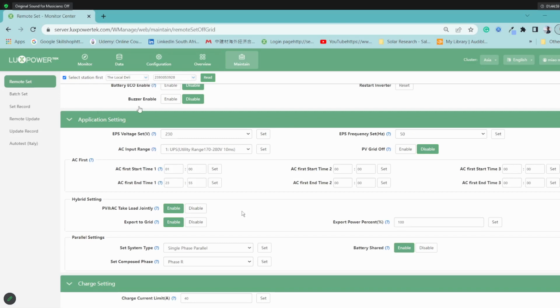Okay, cool. So just to go over AC first again, guys, just to explain: if you activate your AC first, you're going to change the priority of PV power where it will no longer prioritize the load, it will prioritize charging the battery, maintaining its SOC or its voltage if you have it set. Your AC will obviously take the load first and provide power to the battery if necessary, right? But when your panels are generating enough power to take the load off the battery, to charge the battery, then its excess power will go towards load, which will reduce the input consumption from Eskom. And then obviously, if you want to change that around, you need to program this in a way that at a certain period of time, AC first is disabled.